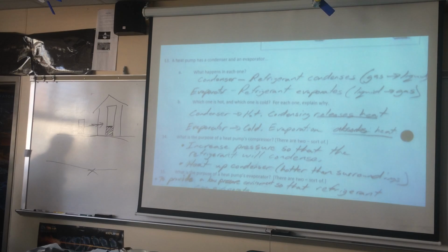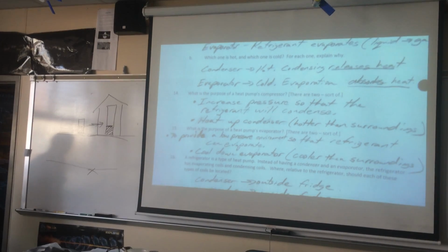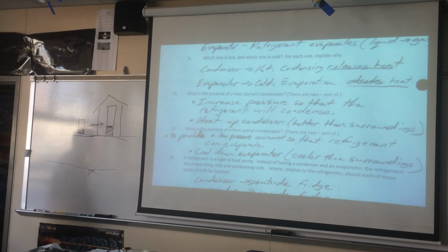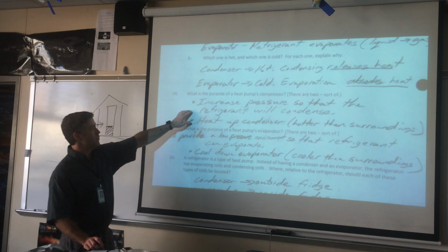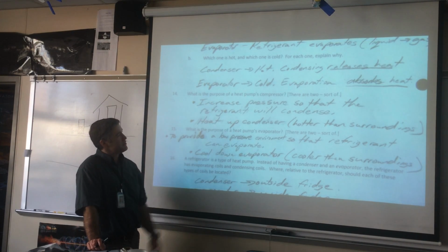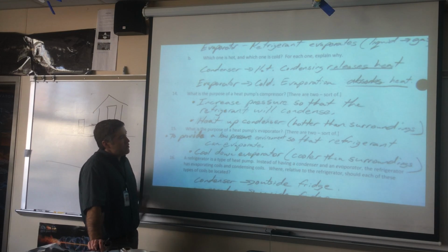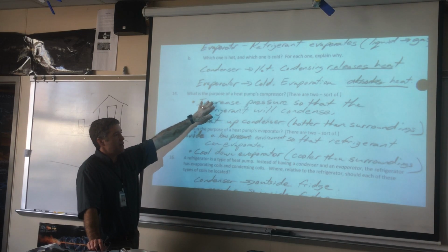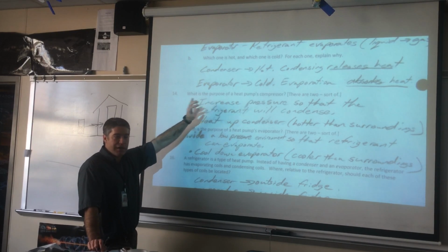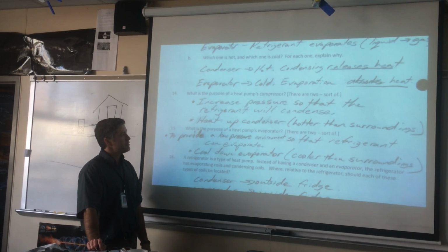Number 14, the purpose of the compressor, this is really the most important purpose, is that it increases the pressure so the refrigerant will condense. When you increase pressure, you make it harder for stuff to boil and easier for stuff to condense.